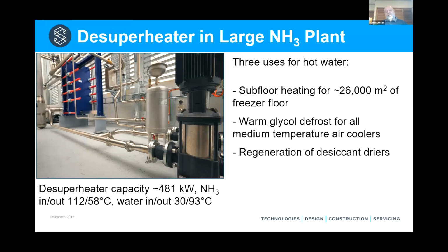So in all the glycol air coolers for the medium temperature services, we have a little heat exchanger so that we can run warm glycol defrost for all the medium temperature air coolers. On one side of that little heat exchanger, we've got the glycol that circulates through the cooler, and on the other side, we have the hot water, and then some valves so that we can, during defrost, generate a closed circuit of warm glycol through the cooler so the ice falls off.